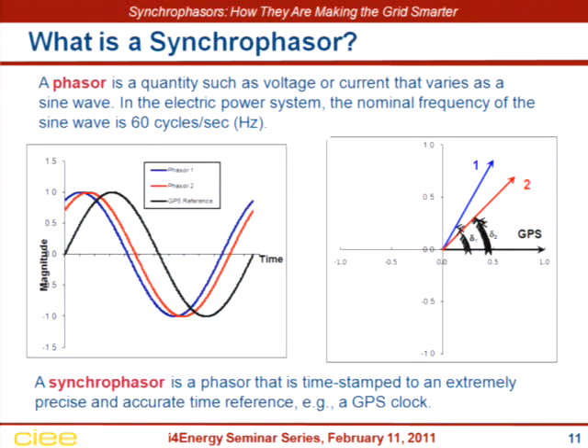These kinds of sine waves have always been measured in the power system, usually with analog equipment, with a certain amount of accuracy. Measurements are used for regular instrumentation, such as system protection, where current and voltage measurements are monitored by protection equipment. If they get out of bounds disastrously, the protection system will operate circuit breakers - I have some pictures later on, though I think I threw too much into this presentation.